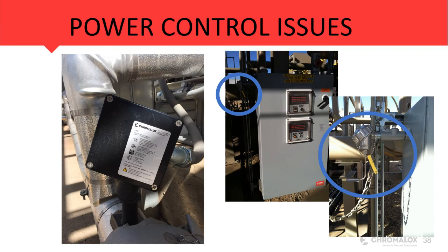So look for these types of issues also. You may want to take a look at that. One good thing to look at in this picture also, as you can see, is someone coped out the insulation to put that power box in, where we're going to get water that's going to go down where that power box is. That's not a good way of doing that. That thing needs to be sitting up on top of the insulation jacketing.